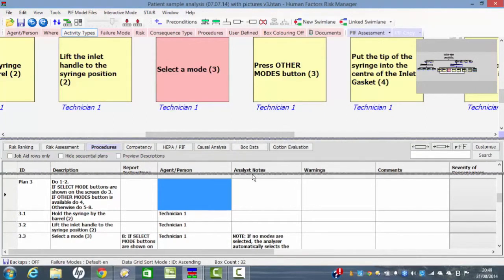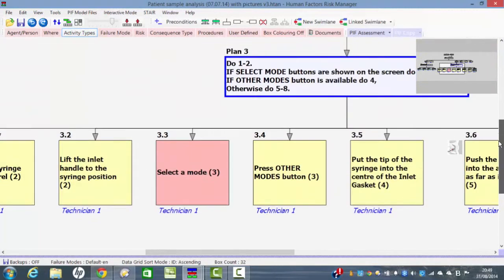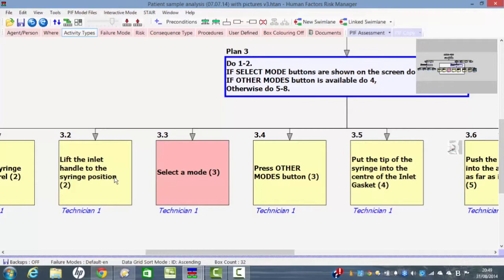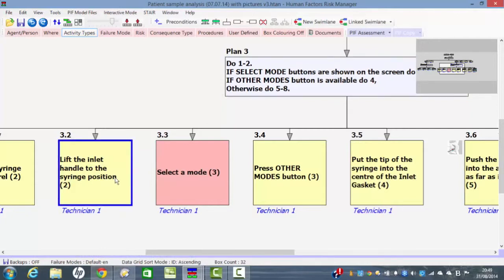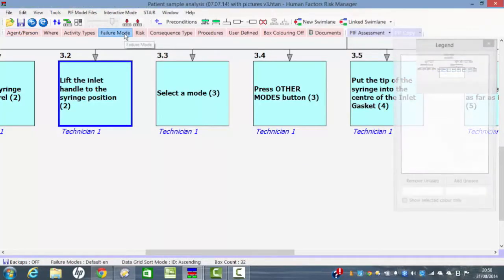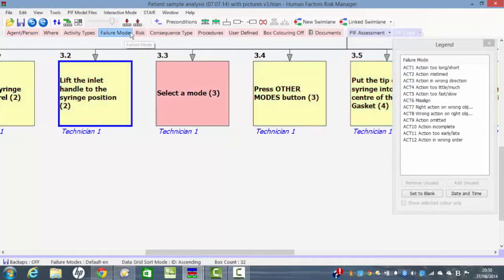But the most important thing is the analysis of potential use errors. So the risk analysis is the second part of the process which I'd like to describe now. So for a moment I'll just remove the table and we'll focus on the steps themselves. So if we felt for example lifting the handle into the syringe position if you made a mistake in that area that would have a significant consequence. We could start to analyze the potential mistakes.